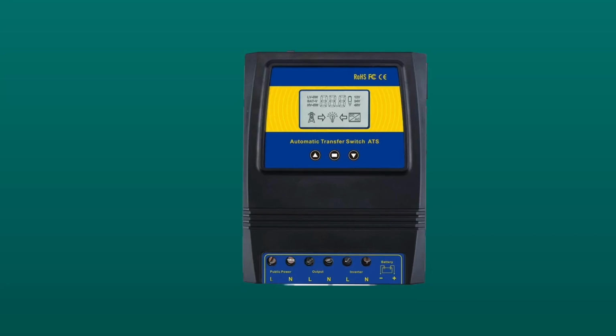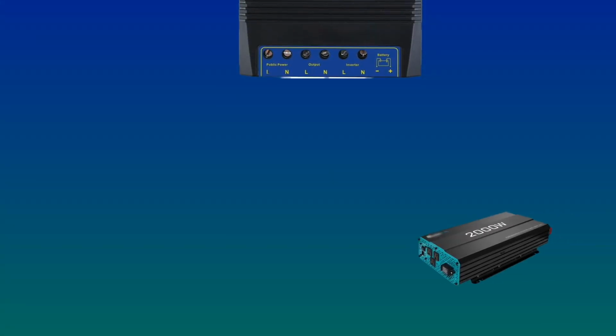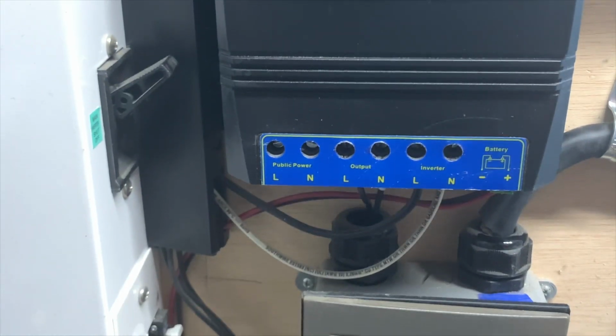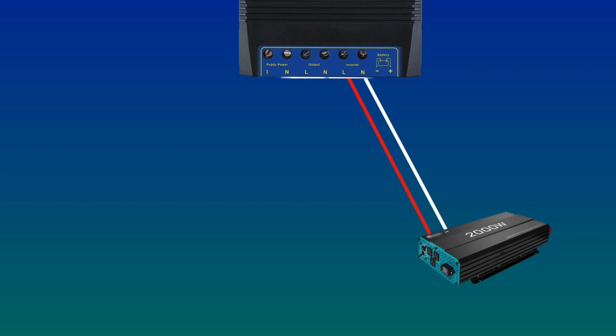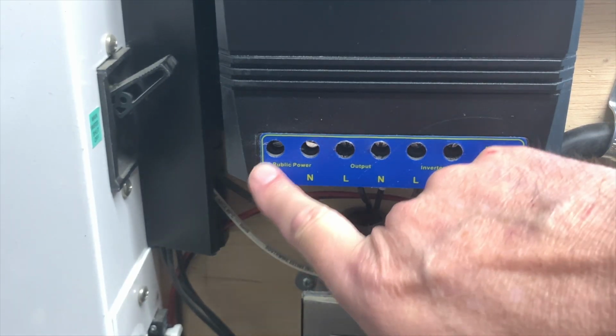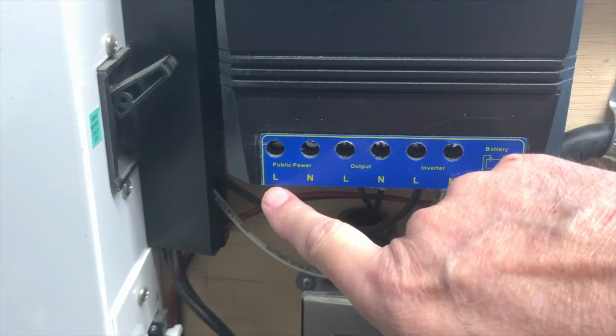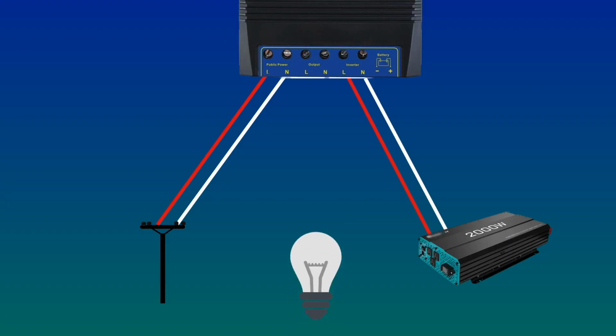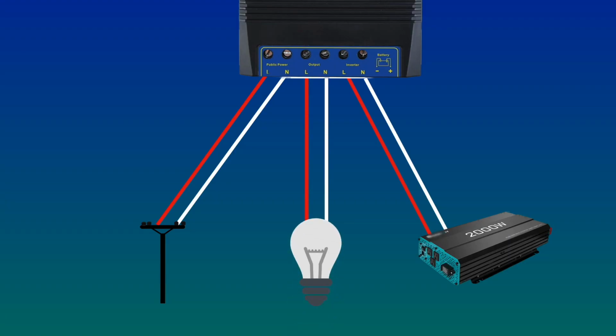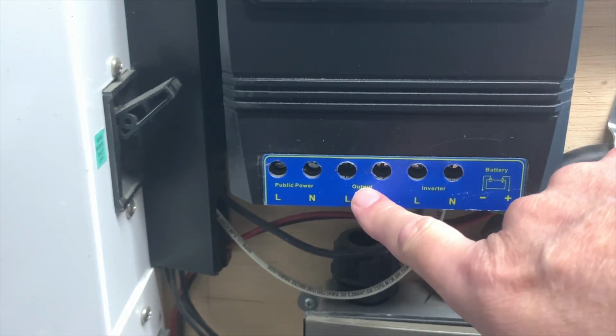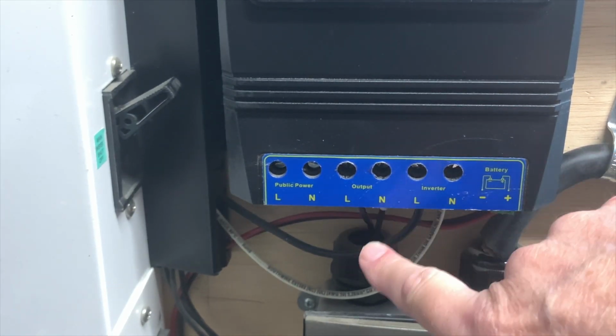Here's how it works. First, take the AC outputs of an inverter and connect it to the inputs right here marked inverter. And notice there's a hot and a neutral. And next, take the AC power from the grid and connect it to this, which is called public power. And again, hot and neutral. Next, connect the things that you want to run off of this, the load, from the middle connectors marked output.